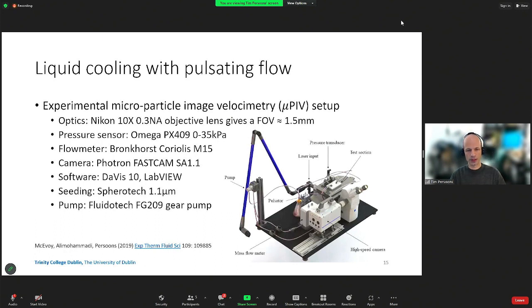So the research here and the link below there shows a paper if you're interested in reading up more on this particular topic. The research was primarily experimental, so we have a micro particle image velocimetry setup over here as shown. So basically it consists of an inverted microscope. Laser light is introduced at the back, and then we have a high-speed camera that is visualizing the flow inside of a microchannel heatsink. I don't think there's anything else here that I have to cover, but the field of view here is something like 1 by 1.5 millimeters. So we're looking at a small segment of a cold plate here, and then visualizing the flow inside the system so that we can quantify the velocity and flow rate.